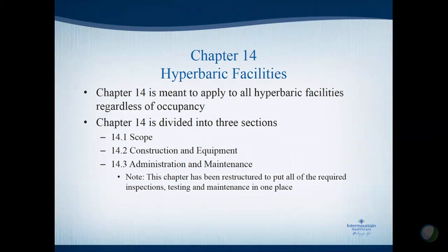what we mean in this chapter is we don't care where your chambers are located. We are all hyperbaric facilities regardless of occupancy. And there's a new definition of healthcare occupancy floating around. We used to talk about healthcare occupancy being more than 4 patients, 24-hour care, more than 3 or 4 days, that kind of thing. Anymore, the definition of healthcare facility is the place that you take care of patients. So it could be a business occupancy, it could be a residential occupancy. This really opens up our chapter for use by the fire marshals and others.